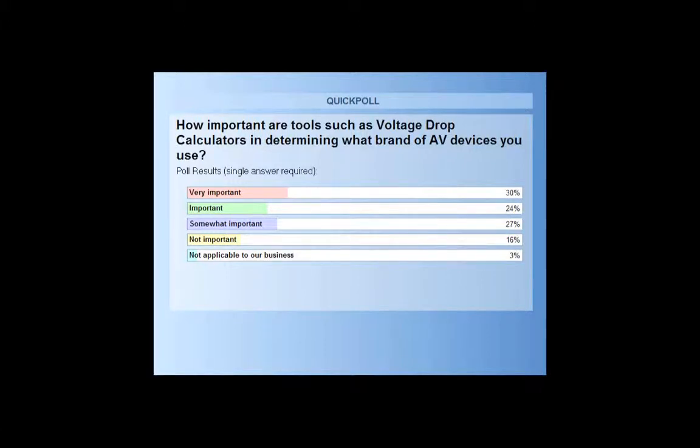Okay. The next question is, can the voltage drop calculator do a Class A volt drop? Absolutely can. That's another field that you saw when you're laying out your circuits. Class A or Class B is also a selection you can choose, and it absolutely does change the calculation based on a Class A circuit. So yes, it does support that.